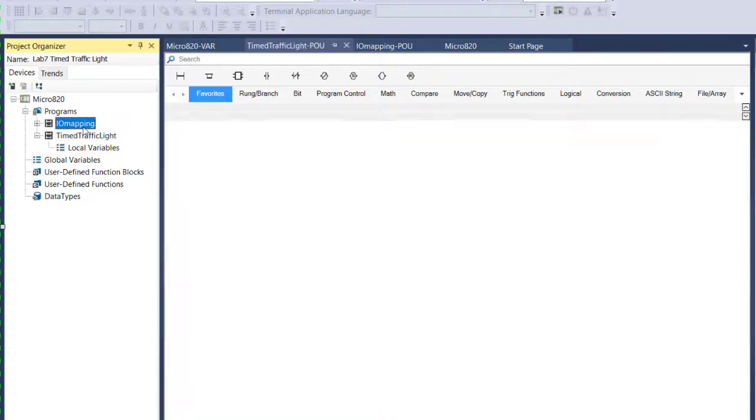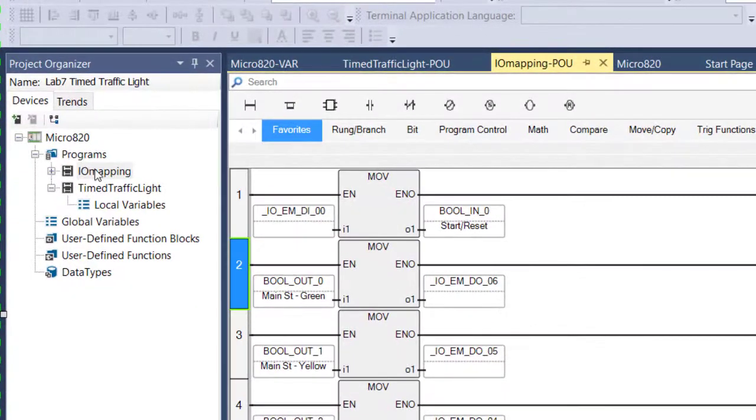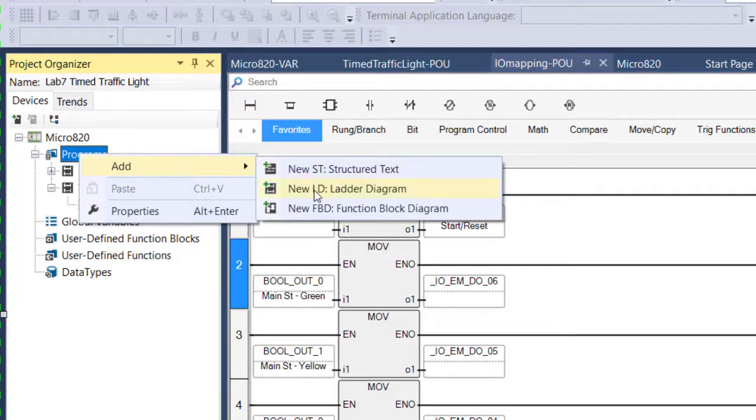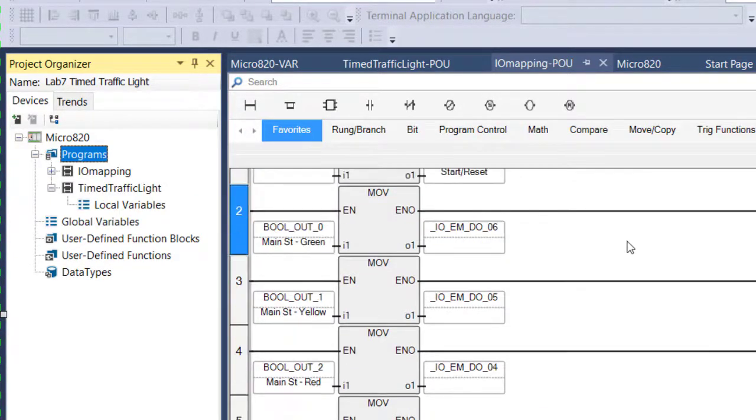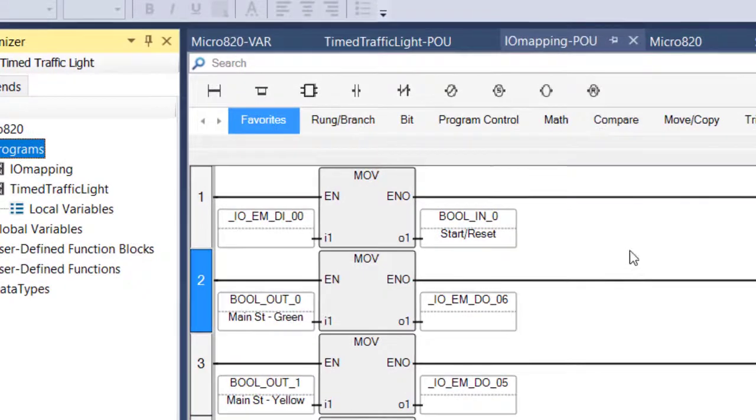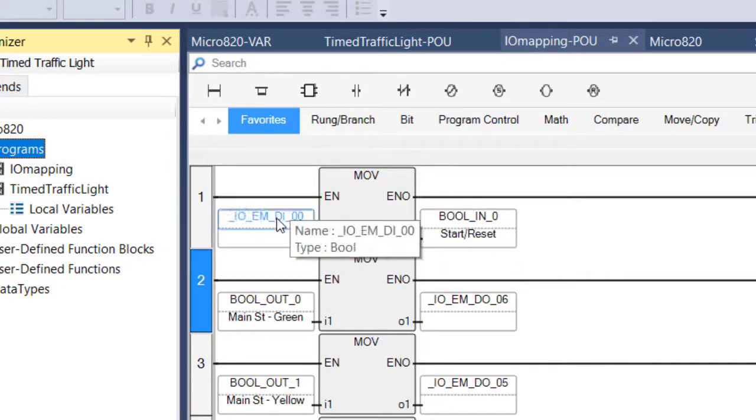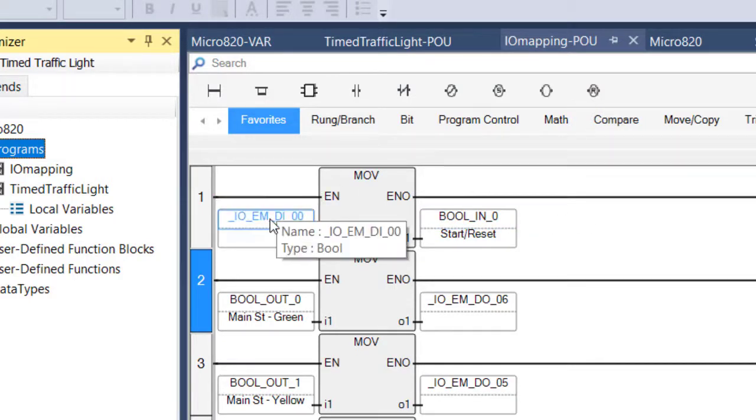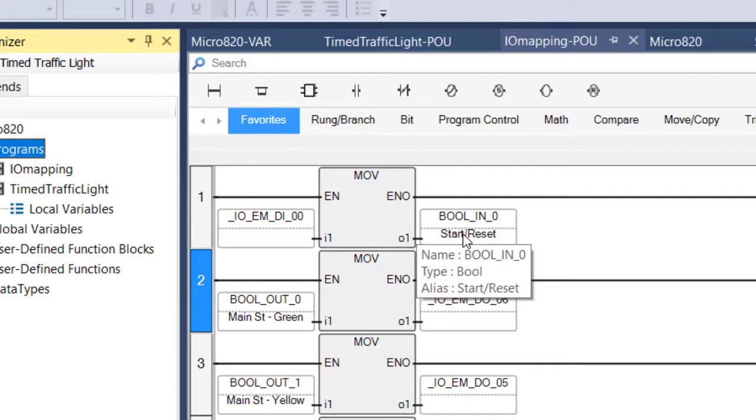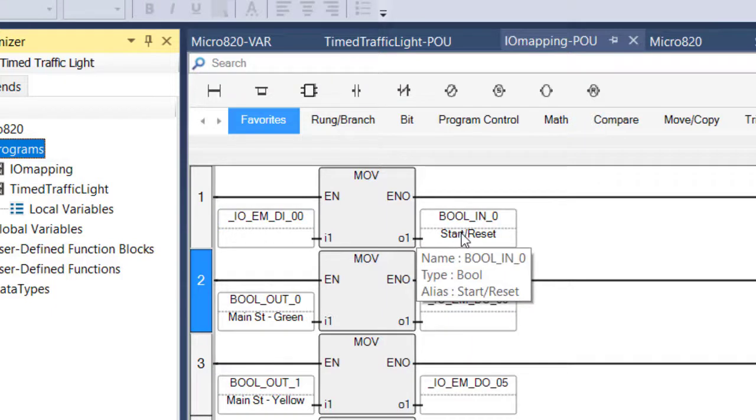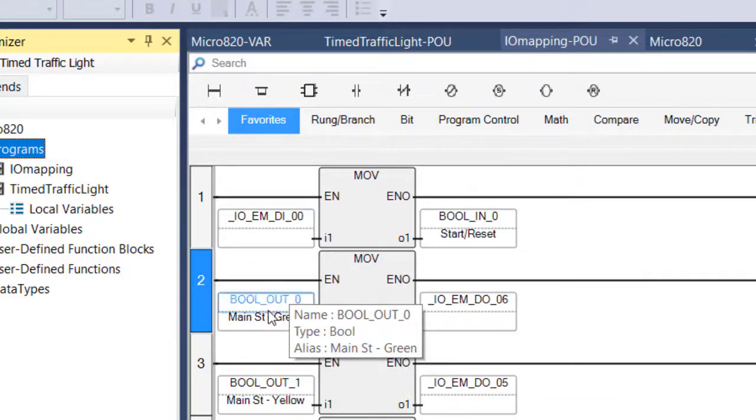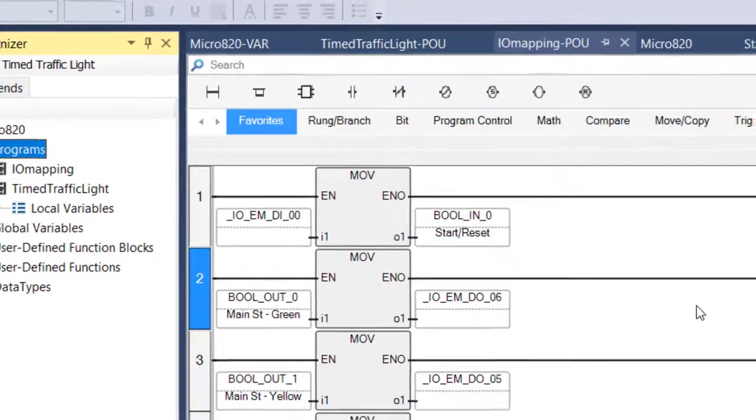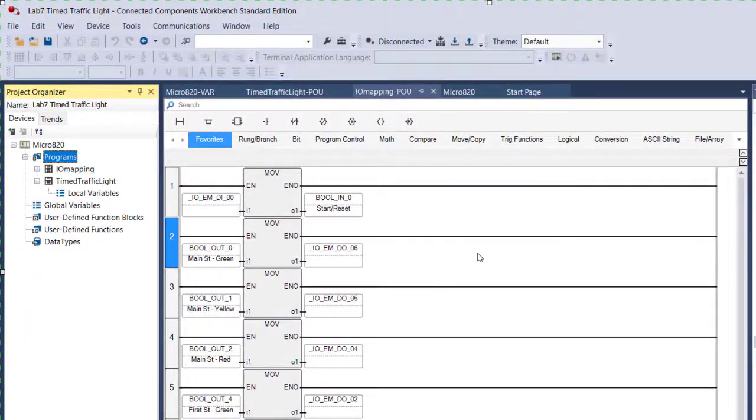I don't have to go to my Timed Traffic Light program, my actual program, and go find every reference to that I/O terminal and make sure I remember to change every reference. That's the beauty of segregating I/O. Write your program to reference global variables, and then after, create a new program that simply maps the input and output terminals to those global variables. The way you create a separate program is you just right click on programs and say add a new program. In this case, I added a new ladder diagram program. You can see within this program there are seven rungs, that's because there are seven inputs and outputs that need to be mapped. I use the MOV, the move instruction, that basically assigns one variable to another. You'll notice with my inputs, this is actually an input terminal on the PLC. So I'm reading an input terminal on the PLC and copying that value into my global variable that's then used in the program. I read the input terminal and send that value to the global variable, and I do just the opposite for outputs. I take the global variable and then I send that value to the output terminal of the PLC. So that's what we mean by segregating I/O. It's very wise programming practice and it'll save you a lot of time and headache later on.